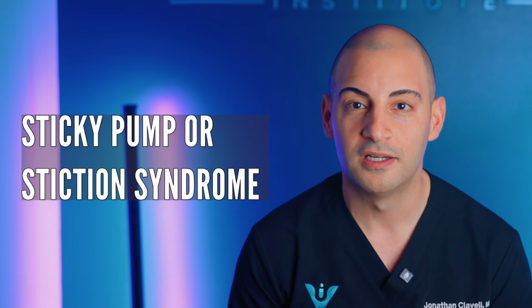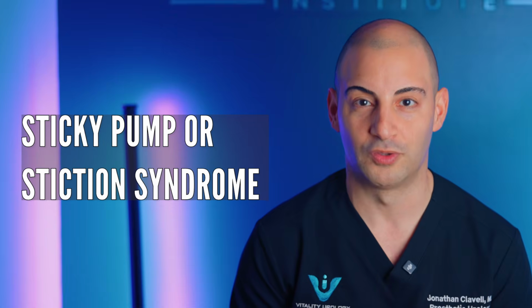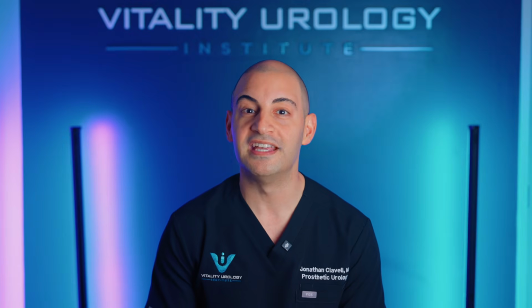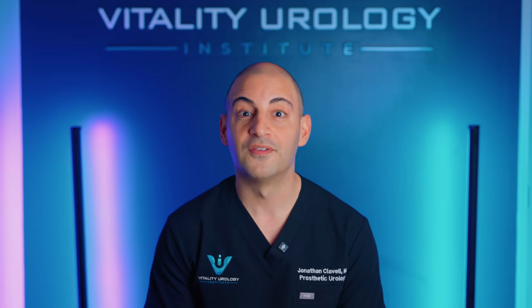However, we have noticed that a small group of patients have encountered challenges with the pump. One of these challenges is that the pump can sometimes get stuck, what we call the sticky pump or stiction syndrome. The sticky pump refers to the condition where the inflation or deflation mechanism of the penile implant pump becomes difficult to operate over time. Sometimes the deflation valve inside the pump may not open easily, requiring extra force to activate it. Other times, specifically when the user has not been cycling the pump on a regular basis and he starts to inflate the implant, the fluid within that system does not transfer as efficiently as we would like. This can lead to frustration in some patients and surgeons and may require additional troubleshooting tips for it to work.